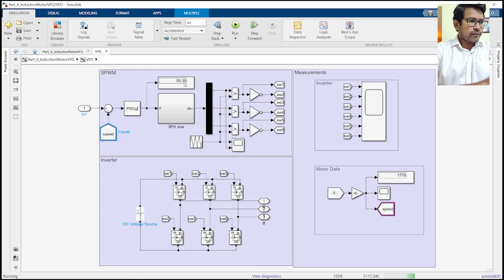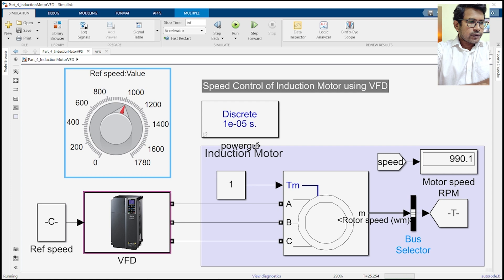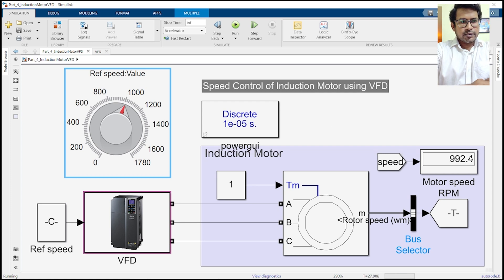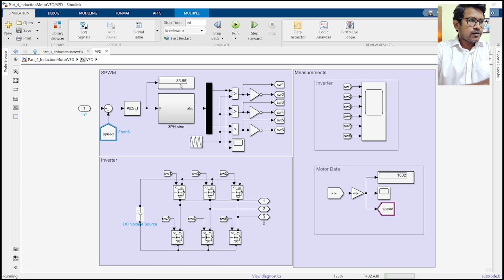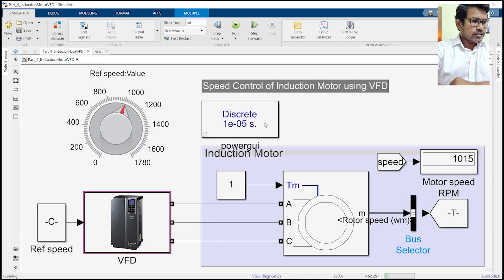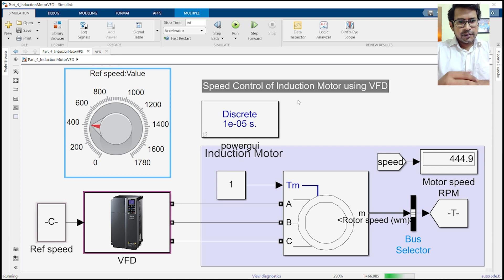If we check the frequency of the VFD, it is almost around 59 or 59.5 Hz. If we change the reference point to, say, 1000, you can see the motor is running at around 1000 RPM. Let's check at what frequency the drive is running — almost at 33 Hz.